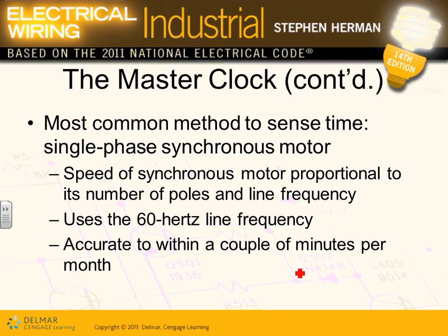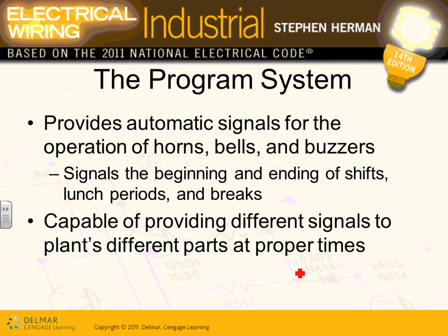The second system they talk about is called the program system. The program system is very similar to a paging system except it sends horns, bells, and buzzers. When you want to signal a break — like in high school when the bell goes off — it's called the program system. It's not paging, though it can interface with paging. Paging sends voice; the program system provides automatic signals for the operation of horns, bells, and buzzers to indicate end and start of a shift, breaks, and lunch periods.